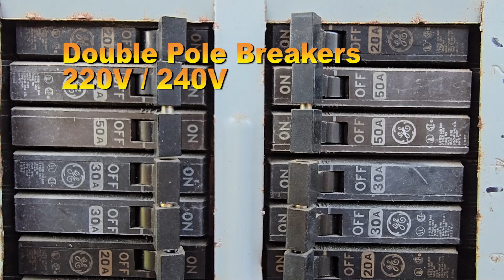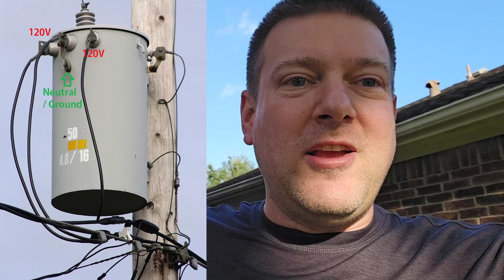So if you think about electricity in the United States, we get 220 volts by taking 120 volts from each leg of a split phase system. The difference in potential is going to be 220 volts. So let's say that you get a dryer. In this particular instance, that's exactly what happened. There was a dryer that was installed at a house, and when they wired it up, the control panel turned on. It looked fantastic. Everything seemed hunky-dory until they tried to run it, and the machine would not heat up.